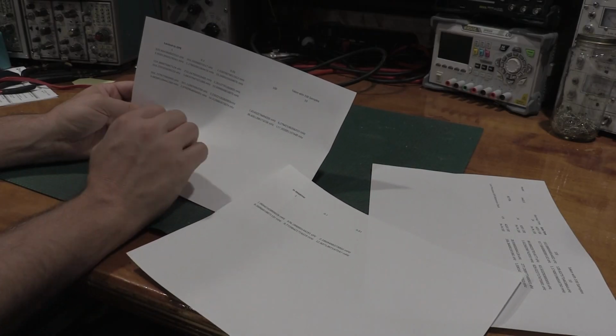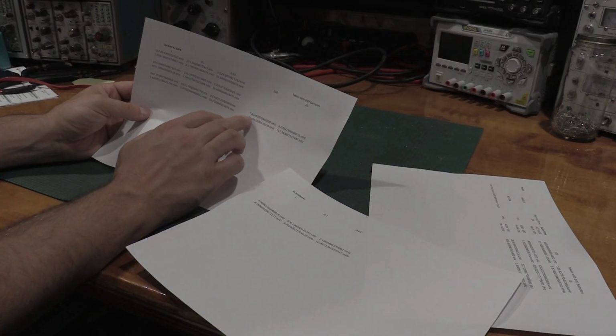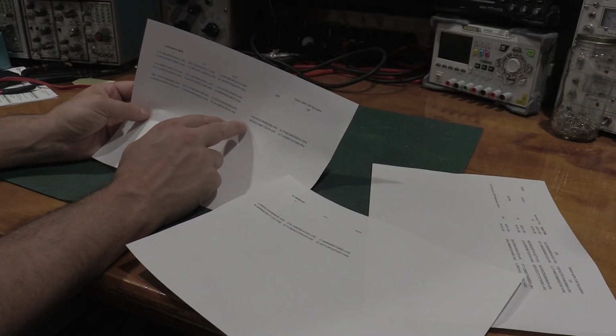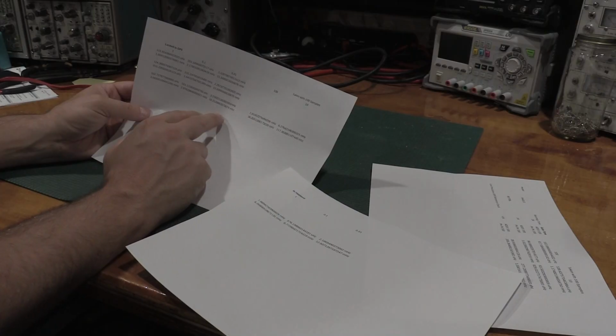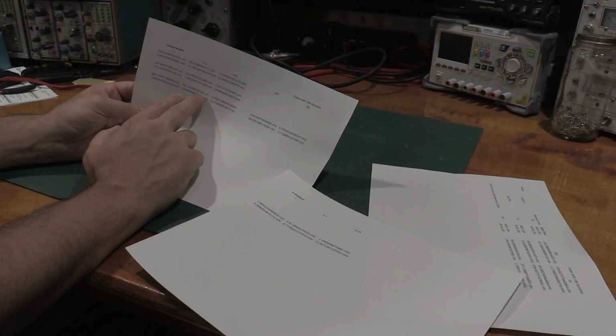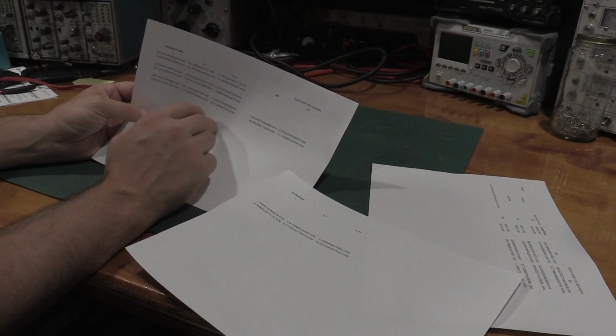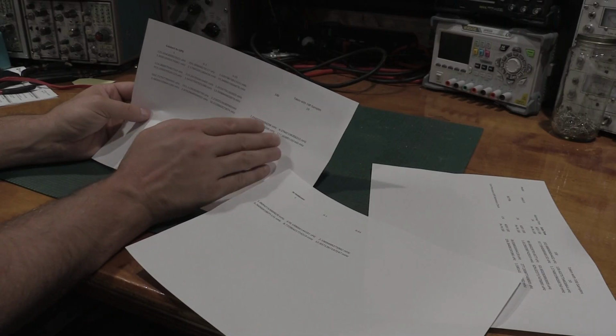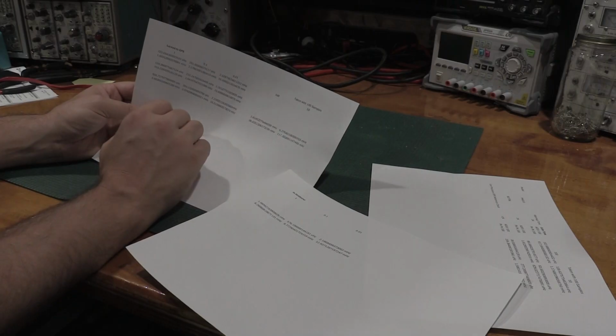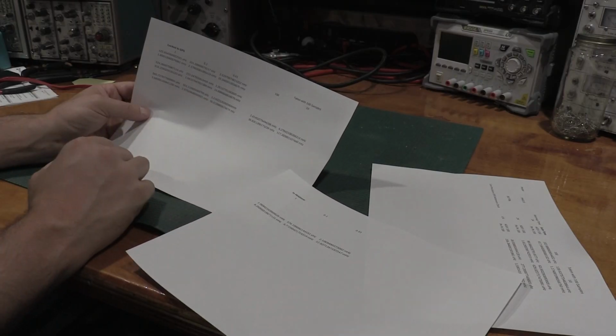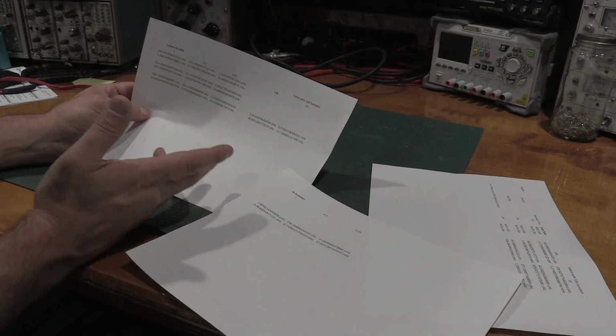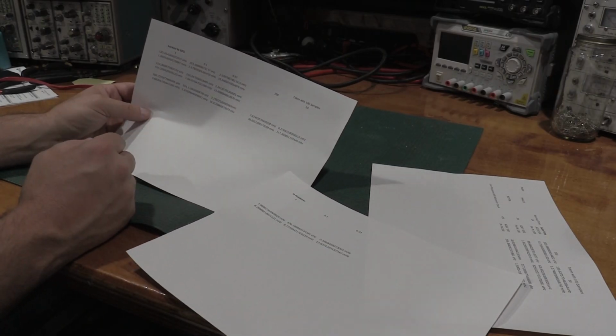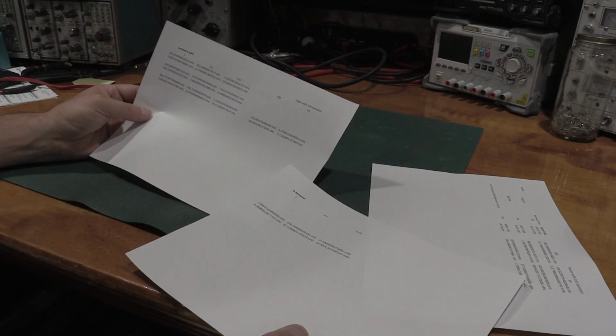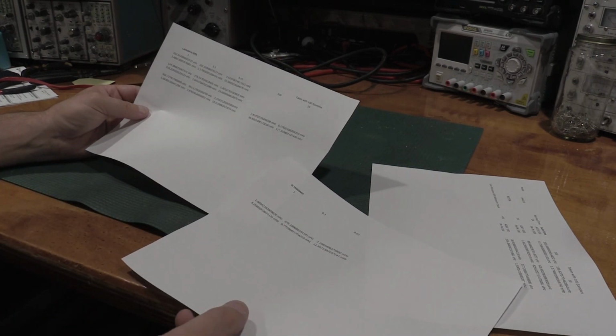We did get into microhertz, but we only got into microhertz on the 0.1 seconds of gate time. Everything else is in millihertz. So where we had 500 microhertz of ADEV when it was locked, the accuracy did degrade a little bit in unlock, which is true for everything. I would expect that regardless of which unit it was. I don't have data points for the other two, but I'm sure their accuracy would have degraded a little bit as well, not being locked to the GPS satellites.